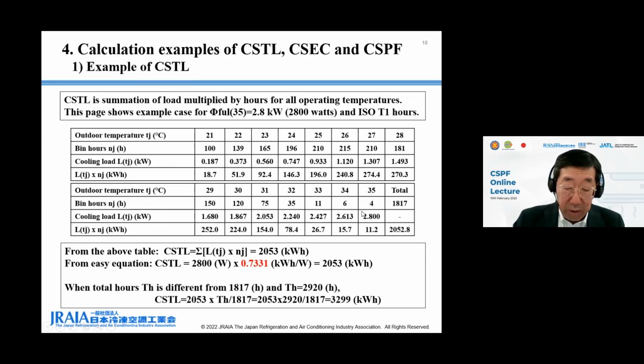The fourth line shows cooling load in the third line multiplied by bin hours in the second line. And the total of this line becomes cooling seasonal total load, CSTL. From this table, CSTL is 2053 kilowatt hour as shown in the lower right-hand row. On the other hand, according to the easy equation of CSTL in the previous page, CSTL is 35 degrees C full capacity 2,800 watts multiplied by constant 0.7331, which also equals 2053 kilowatt hour.